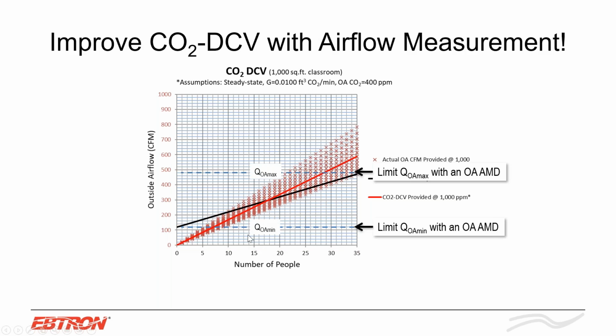Well, a couple things. First thing I always recommend to design engineers is to specify a self-recalibrating CO2 sensor, because all CO2 sensors drift. We have one, but a bunch of people make CO2 sensors out there as well. The second thing to do is limit your max and min flow rates based on the space type of application and the max population on the high end and your min population on the low end, right? That way, you are never over-ventilating your space, you're never under-ventilating the space, and everything in between you are controlling with your CO2 sensor. So that is a control strategy that certain engineers are implementing, again, to save energy and not under-ventilate the space on lower populations.